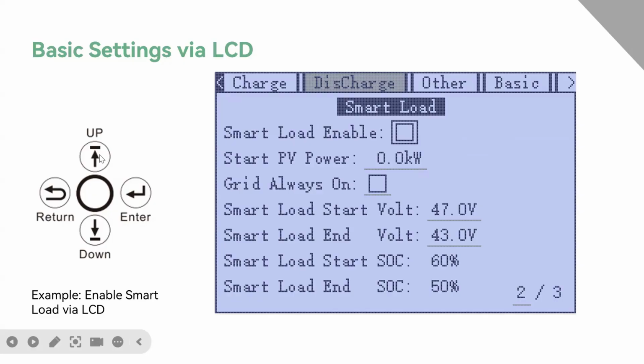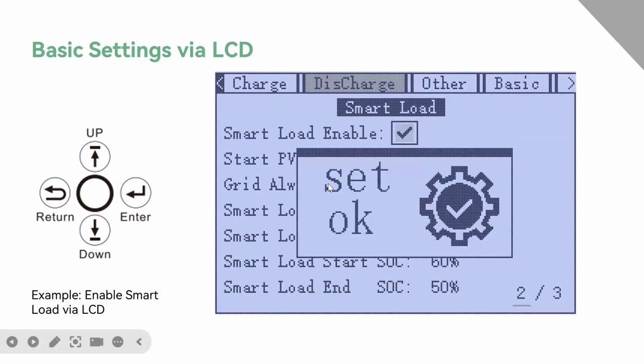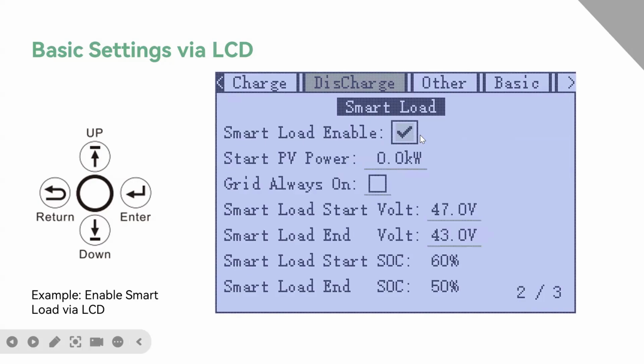In this page, you can also use up and down to set different applications. In this case, we just need to enable it, so we don't need to use up and down. Just hit enter again, and when the column turns gray, it means we can use up and down to choose between enable or disable. In this case, we need to enable the smart load function. When it is checked, we enter again, and it will say set OK. After we set OK, you can see that the smart load is already enabled. So that's the whole procedure to change one setting through the LCD.